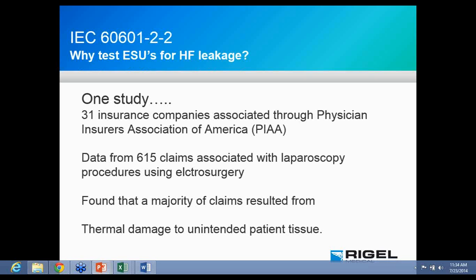So what kind of problems happen? Well, there's a risk to the patient. Capacitive coupling can be in part responsible for serious patient complications. Now, manufacturers go to great lengths to minimize this. So they use active electrode shielding, dispersive metal cannulas, and sheath guide wires. One of the easiest ways to do this is to use bipolar active electrodes. A bipolar really narrows down the area where the current flows, and when you have such a localized application of RF energy, it's much easier to reduce the risk that way. So that's the benefit of bipolar in a nutshell.